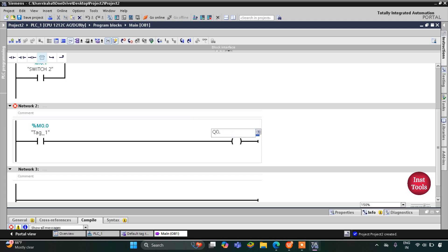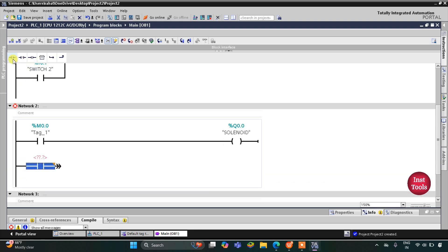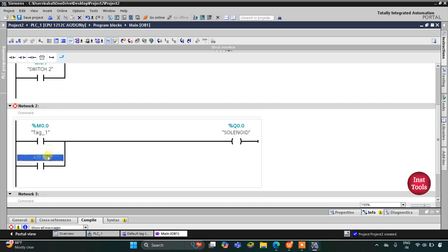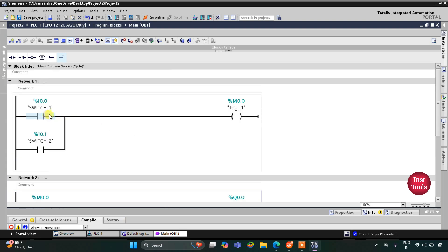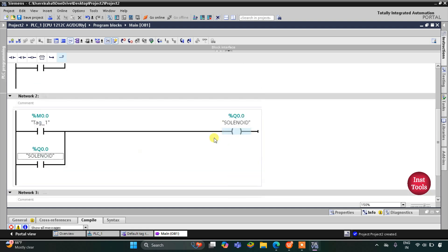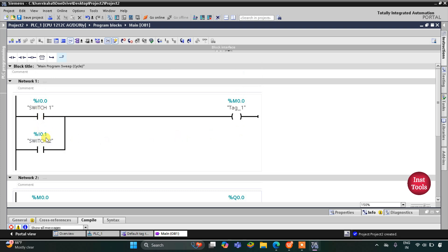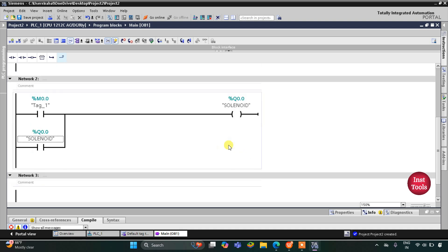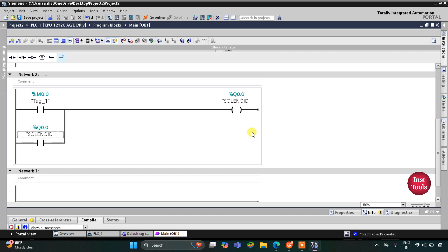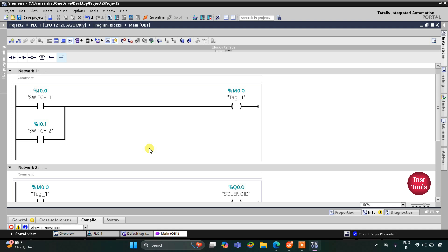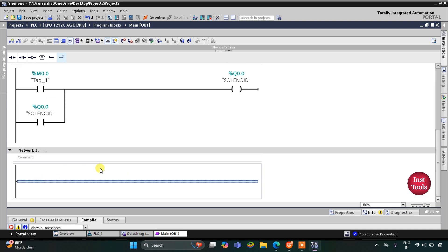I'll insert a normally open contact for M0.0 and then insert a coil for the solenoid — that is Q0.0. Then I will latch it: open a branch, add a normally open contact for the solenoid (Q0.0), and close the branch. When Switch 1 is pressed, M0.0 gets energized and the solenoid turns on. When the switch is released, M0.0 drops off, but due to latching, the solenoid still remains on. Now for the second press, we will use one more network, starting with a normally closed contact.